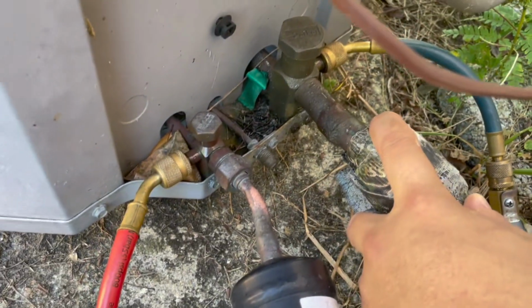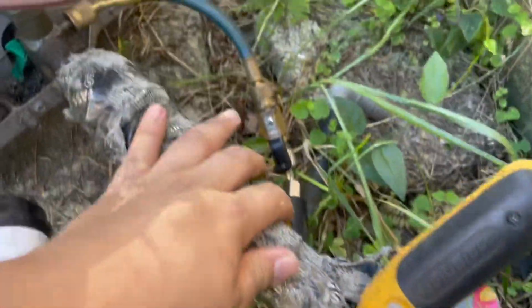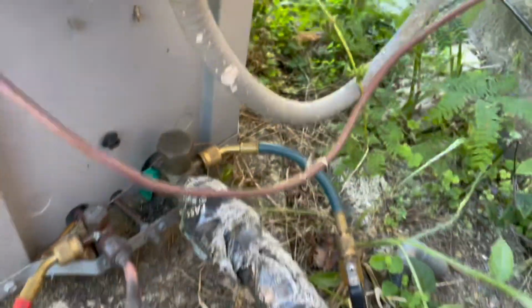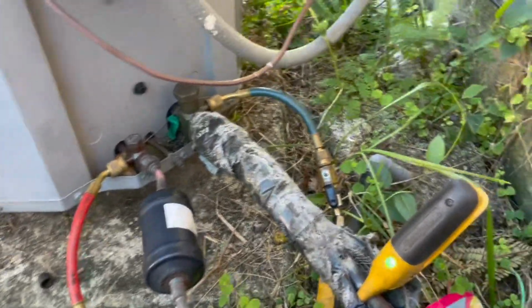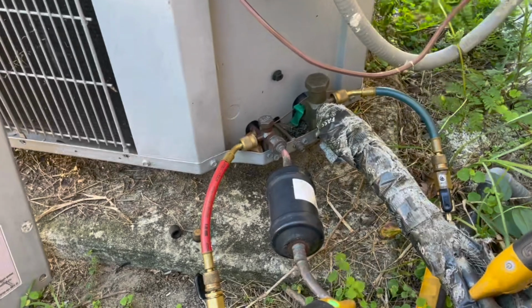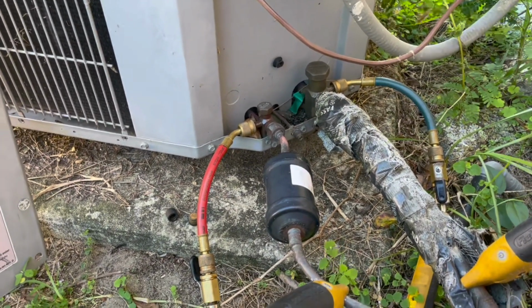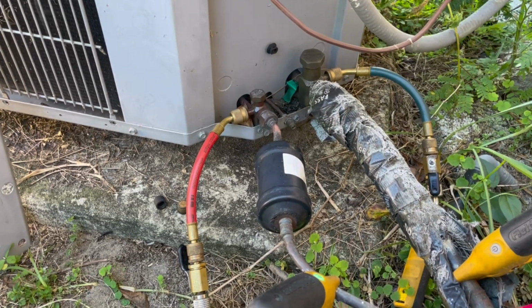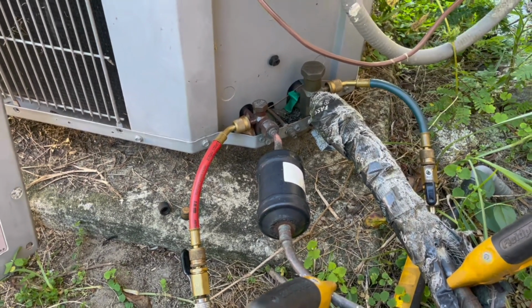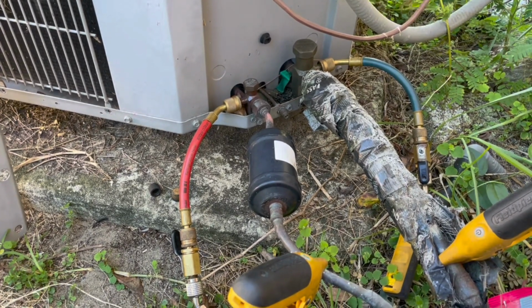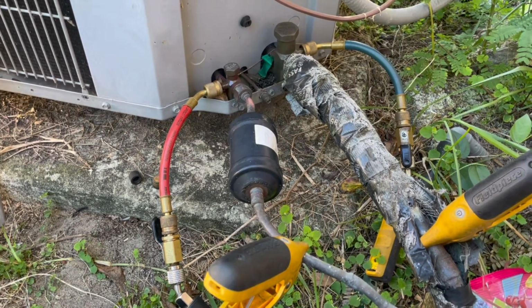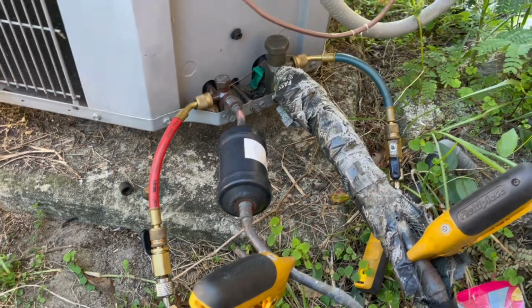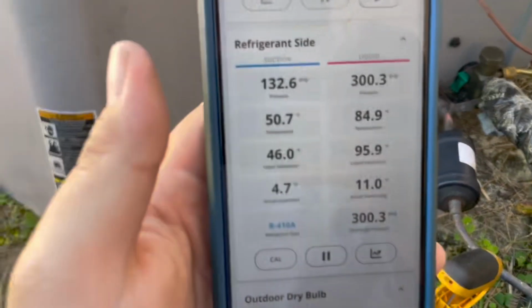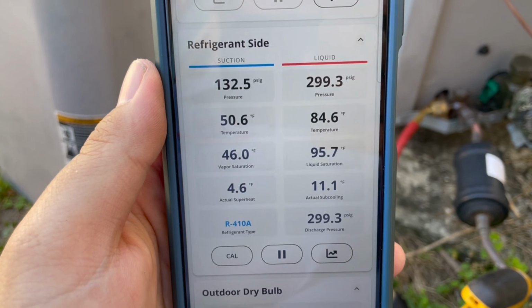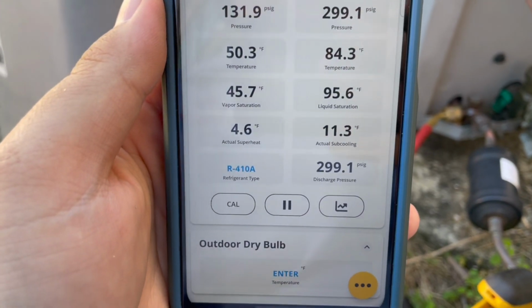Okay, so I changed my mind. I'm just gonna look at it while I'm here. Something I noticed, it looks like the line set, the suction line's undersized. It looks like they've got 3/4, and it looks like it's supposed to take 7/8. Let's see what this thing's doing. Let's see, job length. Okay, so it seems like it's working. Don't see real problems with it. Subcooling looks good. Pressures look good. Superheat's a little low.